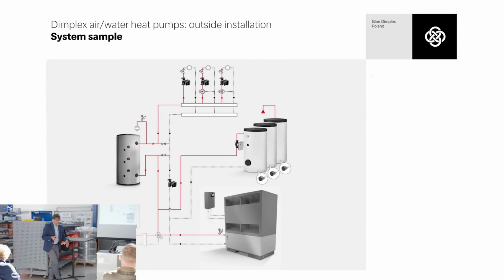This is a simple example of how the system is set up with the typical functionality: the heating for the house and the production of domestic hot water. We have the outdoor monoblock heat pump here as the heat source, and the controller, of course, inside the building, some buffer tank, some circuits, internal installations, and some domestic hot water cylinders.